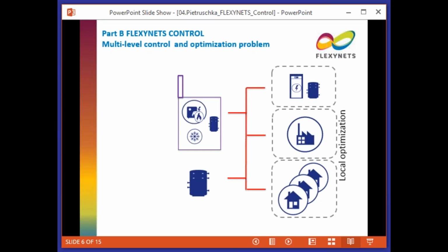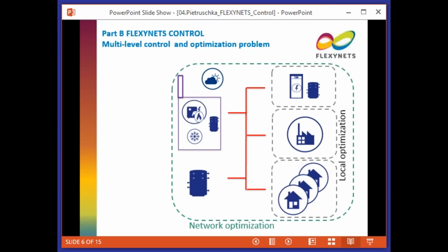Then they are connected to the network, and we have some heat supply because the different sources are not always equalizing the needs of demand. So we also need some centralized sources which can be connected to equalize demand and supply, and some storages where we can store excess heat in the network. This is the network balancing, where we need to keep the network in an operational situation so it always can provide what is needed at the different substations.